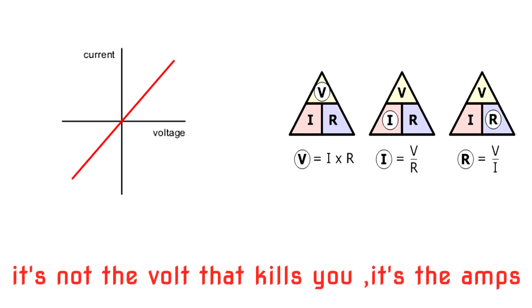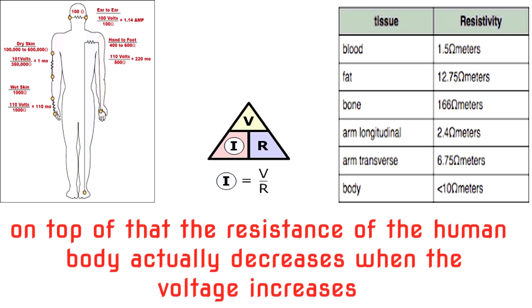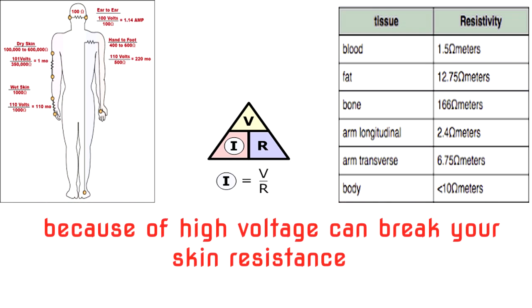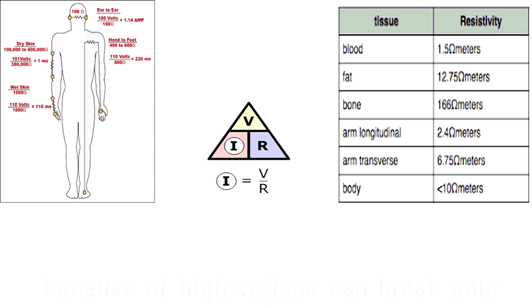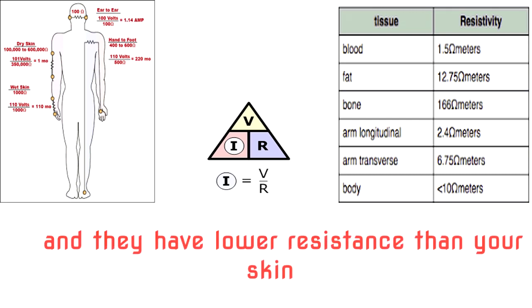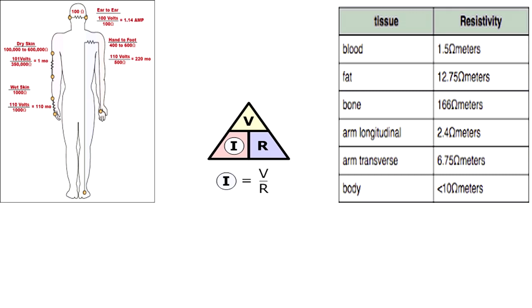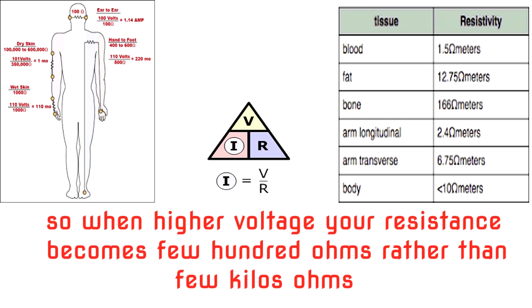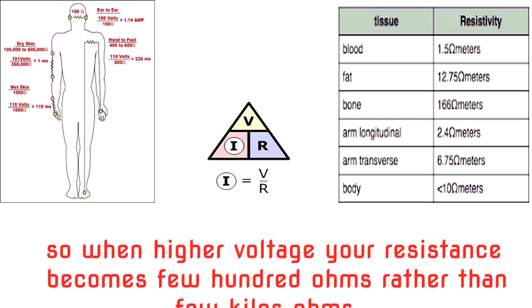On top of that, the resistance of the human body actually decreases when the voltage increases, because high voltage can break your skin resistance. Under that skin there is blood and veins, and they have lower resistance than your skin. So in higher voltage, your resistance becomes a few hundred ohms rather than a few kilohms.